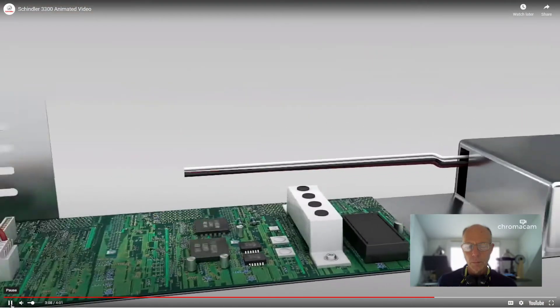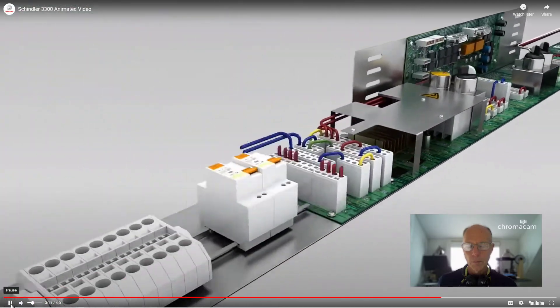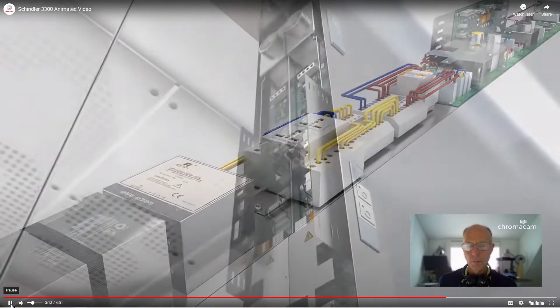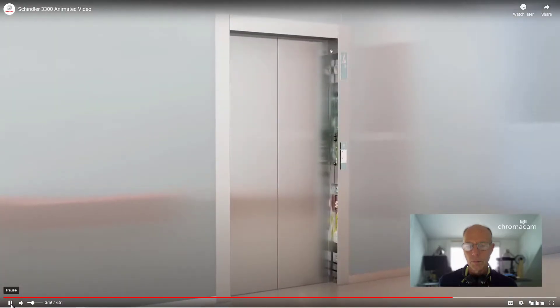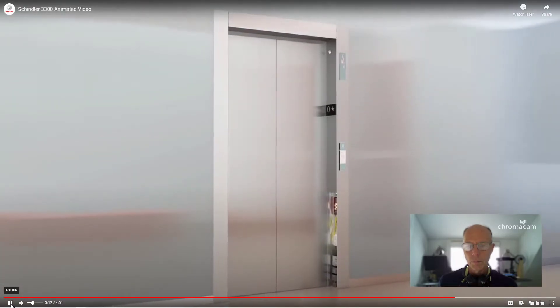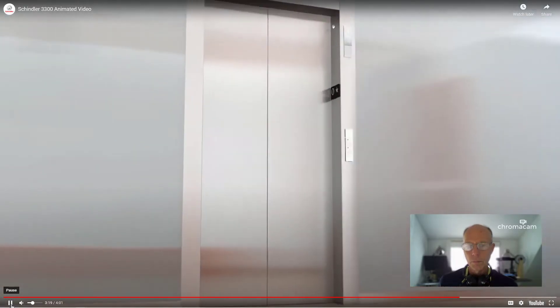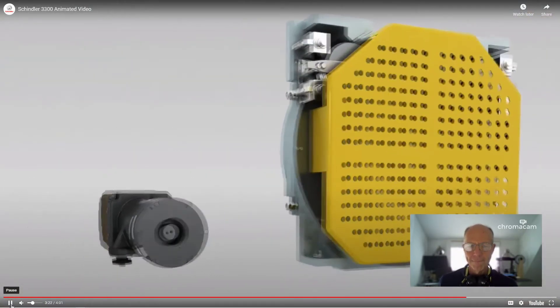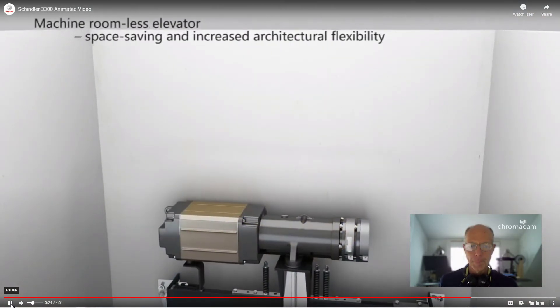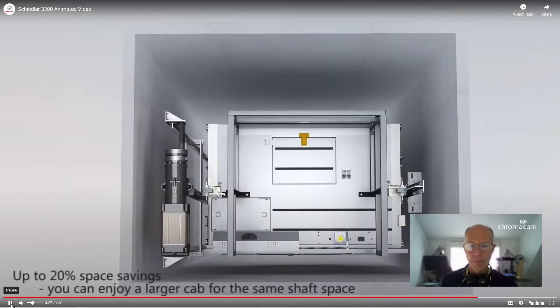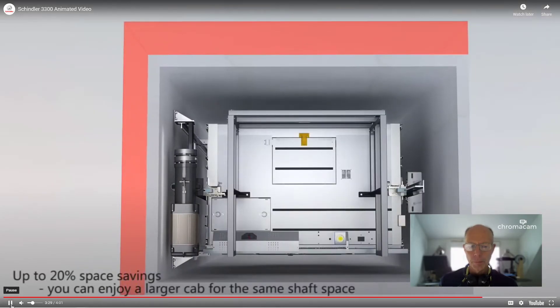Blending their products into the building environment — the Schindler 3300 inspection and test panel is installed in the door frame on the top floor. An additional control cabinet is not needed, which in turn provides more usable space and enhances building aesthetics. This machine-room-less elevator is designed to minimize its entire operating space by having very small suspension pulleys at the bottom of the car.